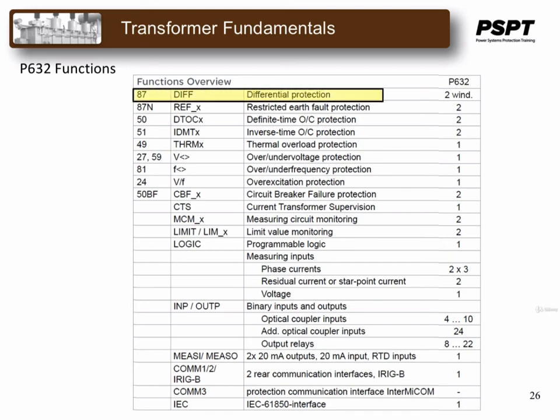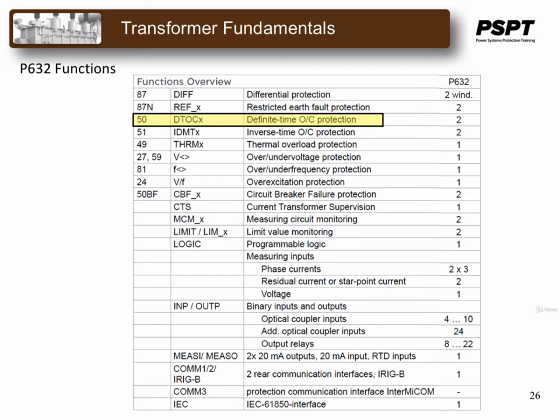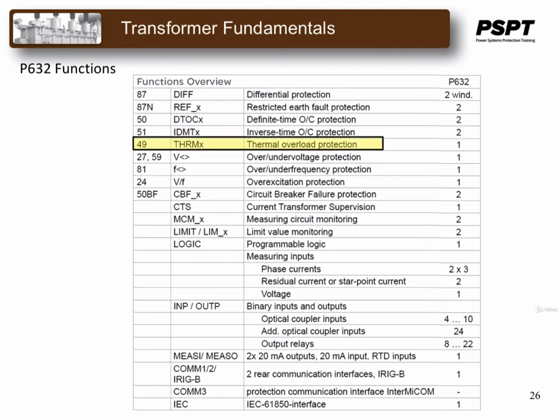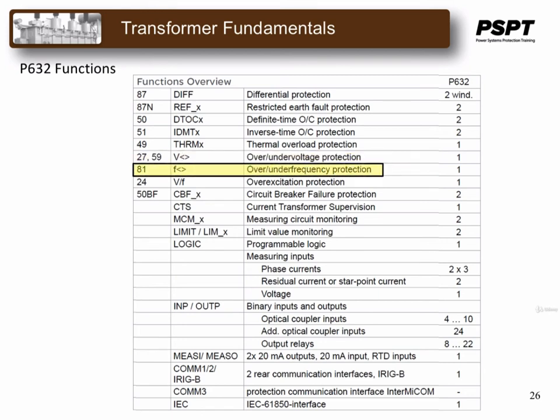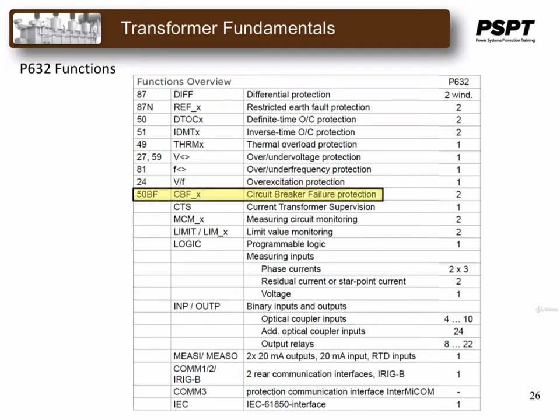Protection-wise, it has differential protection, restricted earth fault protection. It has definite time overcurrent protection, as well as inverse time overcurrent protection. It has thermal overload protection, over and under voltage protection, over and under frequency protection, over excitation protection, and it has also capability of using or having circuit breaker failure protection built into it as well.